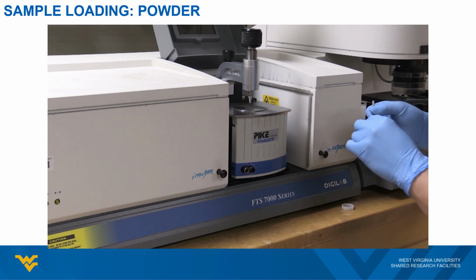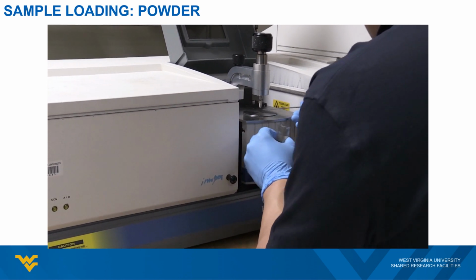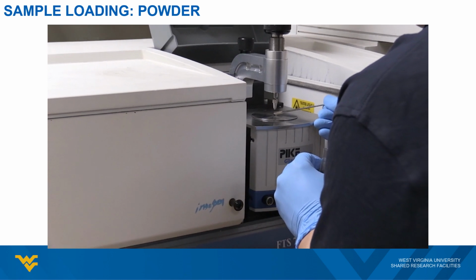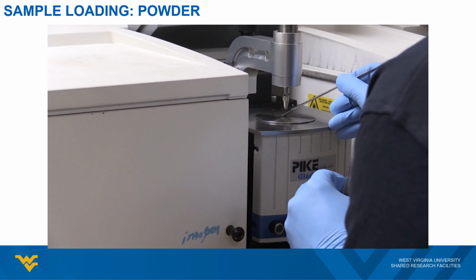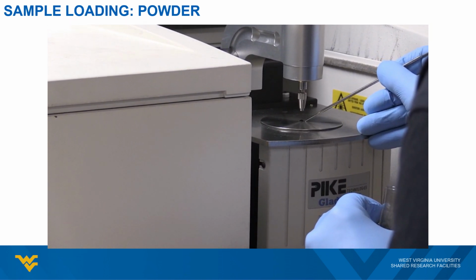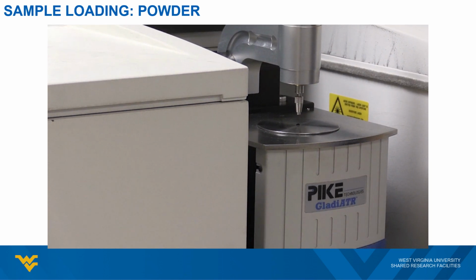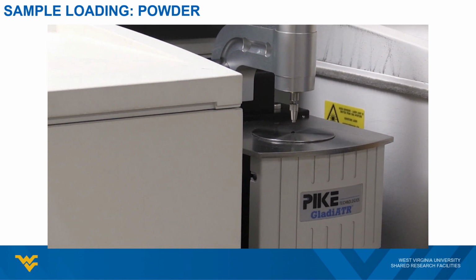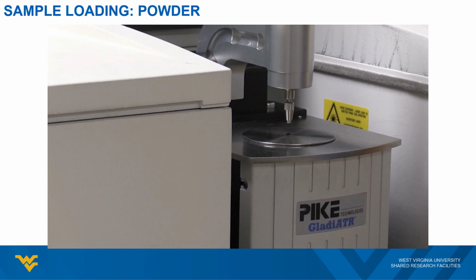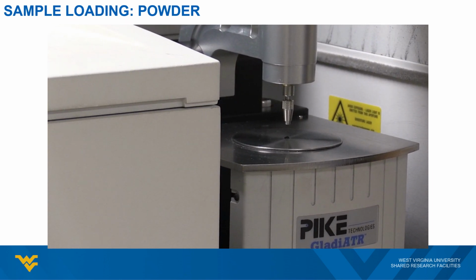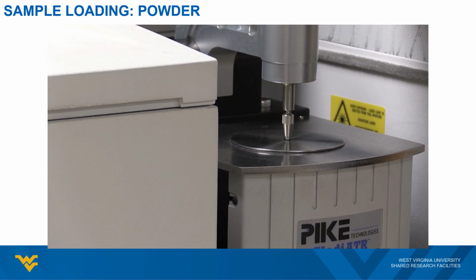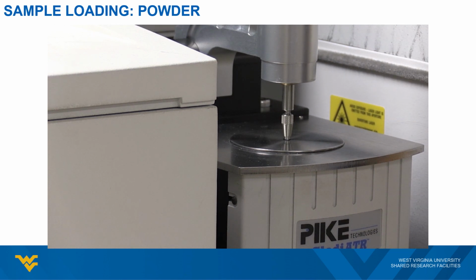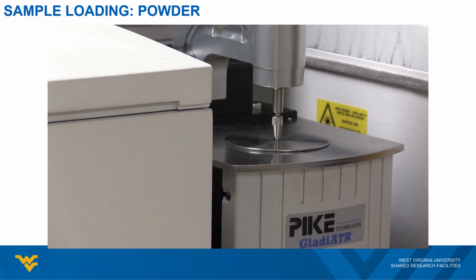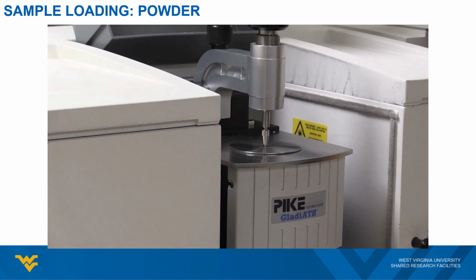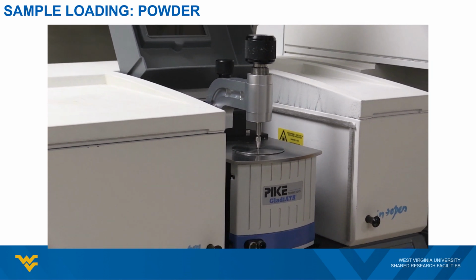Apply a small amount of powder so it covers the diamond window. Then close the clamp by rotating the knob on top. The clamp is designed similarly to a fuel tank cap. Rotate the knob until you hear a click sound. This click sound signifies that the clamp is securely in position.